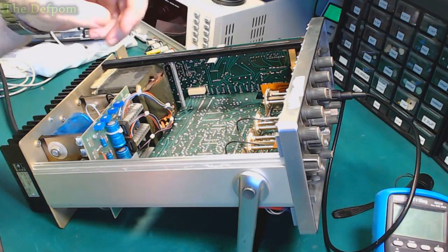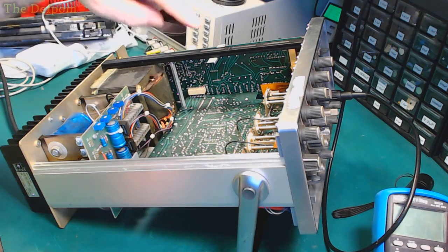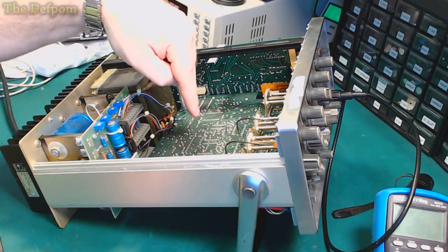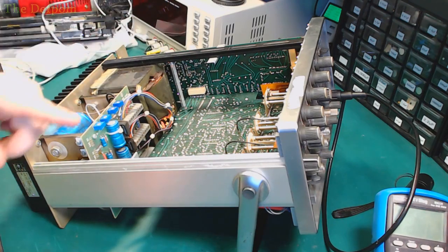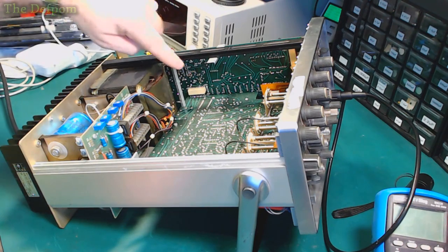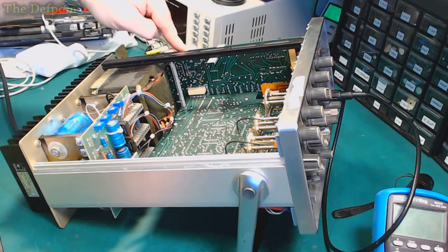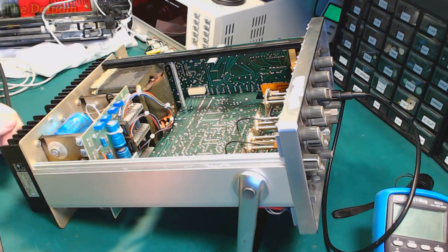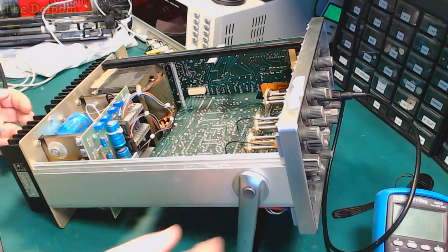Now, according to the diagram of the 5715, the 100 series board, which is this one here, is the control circuitry, and the 200 board is the output board. Now this looks like it's got the same number scheme. So this is BU240, that connector, which means that's the 200 board. So I believe that's the board I need to be looking at, which is nice and convenient because it's on the side, it's easy to get to.